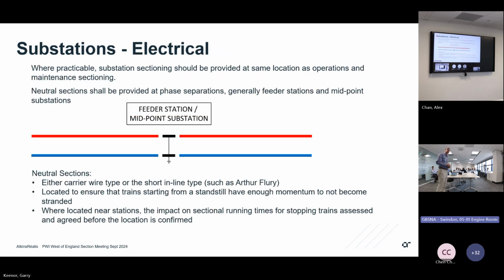At substations, we do need sectioning at substations. And we're specifically talking about now the feeder station, so the substation that has the incoming supply from the grid, and also the midpoint substation. So that could be a midpoint AT site or a midpoint track sectioning cabin if you're on classic. So we will have sectioning there. You should try and align the substation sectioning, and it's usually a neutral section as we've shown here. You should try and align it with your isolation requirements.